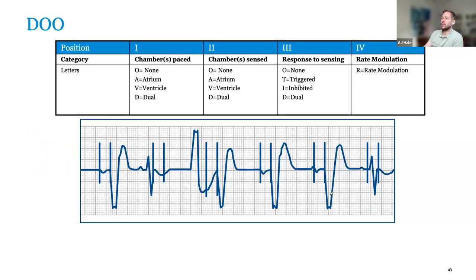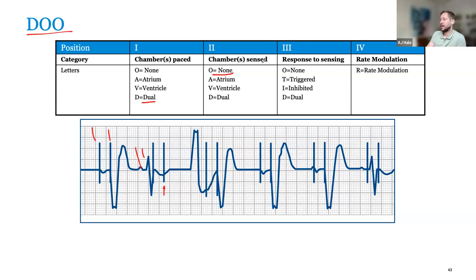DOO is like VOO or AOO except we're pacing in both the atrium and the ventricle. We see atrial capture, ventricular capture, timer waits. The device doesn't sense at all. It then paces in the atrium and then paces into the ventricle right in the T wave — which is one of the risks of using asynchronous modes, as it could be proarrhythmic. This is why whenever you program DOO, VOO, or AOO, you always want to program above the patient's intrinsic rate to suppress PVCs and reduce the risk of pacing into vulnerable periods.